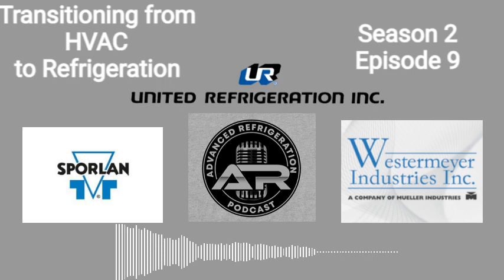The nice thing about the Sporlans is, say you have a non-adjustable expansion valve, because for some god-awful reason somebody had this genius idea, and they're all over Chicago still. So I keep a couple on my truck, so if we do a case change or a case move and it's like, now this case is 2 degrees colder, you've got to go in there and adjust the valve. At least you could drop the bottoms on there without having to change all the valves.